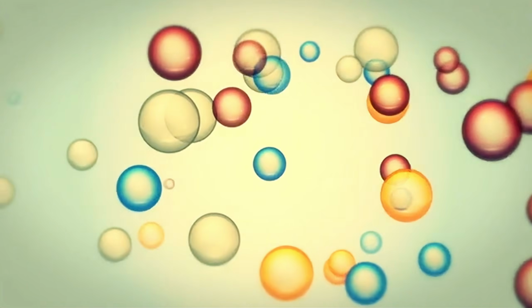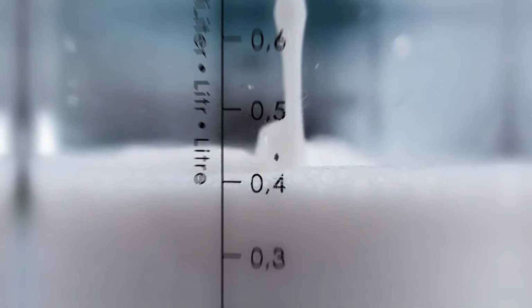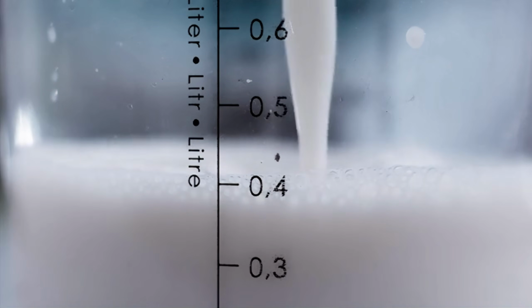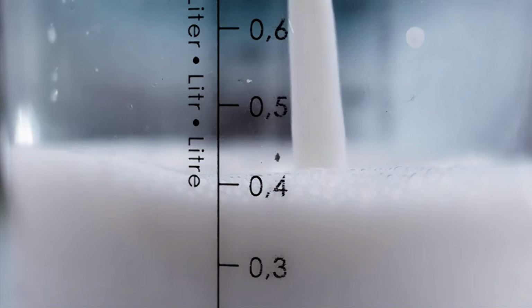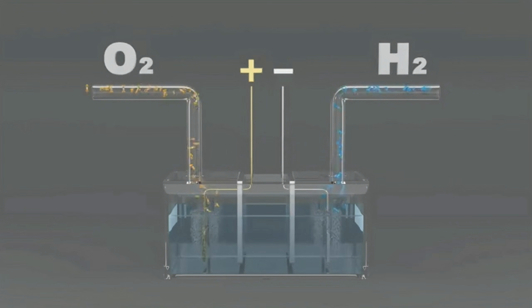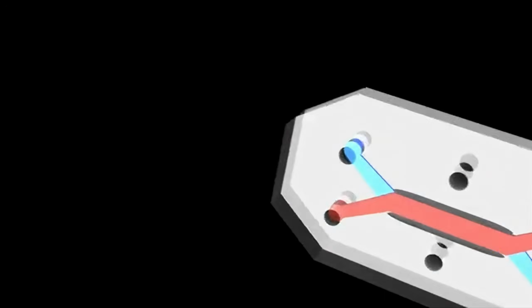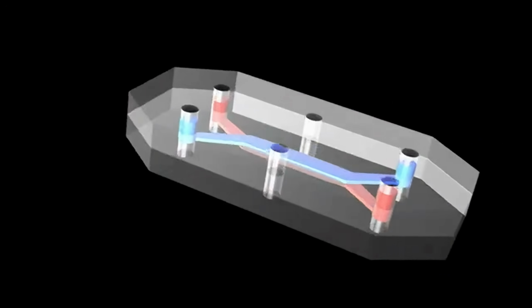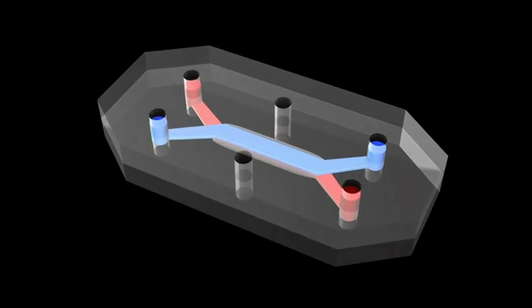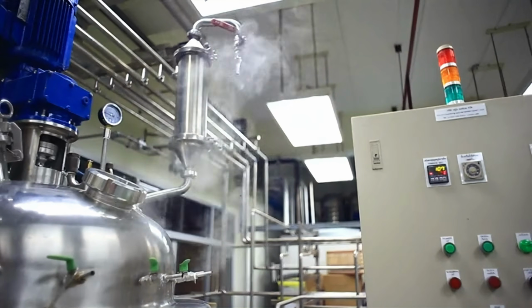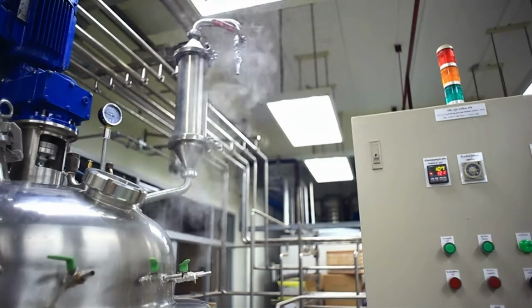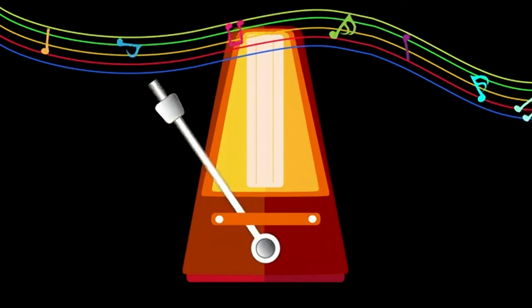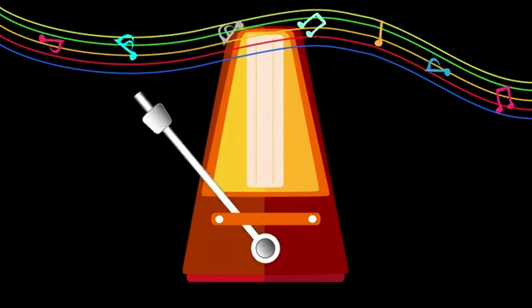Certain liquids will absorb certain gases enormously well. Ammonia gas dissolves into water with remarkable eagerness. Water vapor is absorbed by a lithium bromide solution the same way. So instead of squeezing the gas mechanically, you let it dissolve into a liquid. The gas disappears into solution, which does exactly what a compressor does, meaning it removes the low pressure vapor from your evaporator and lets more liquid evaporate. Then you take that solution, apply heat to it, and boil the gas back out under pressure. From that point, the cycle continues exactly like a conventional system.